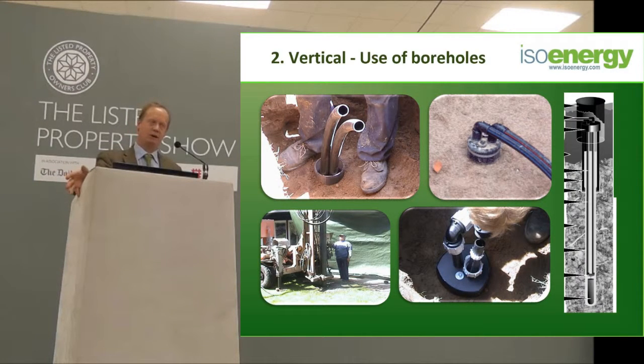In Sweden there is now a law that every time you dig a borehole, you must put heat back into the ground in the summer to compensate for the cold you've been extracting in winter. It's easy to do because Sweden has warm summers and cold winters — you can run the whole system in reverse to cool buildings in summer and recharge the ground. In certain areas of Stockholm this is now mandatory by law, because they were beginning to cool the rock.